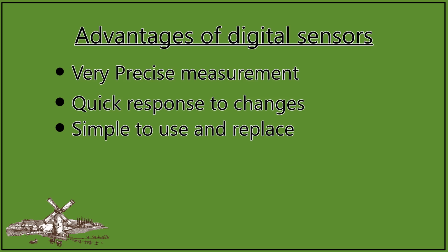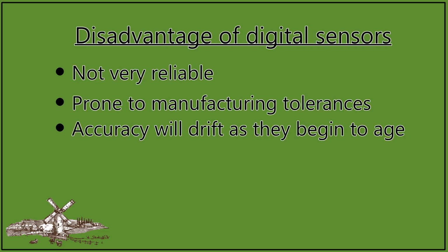Now, the disadvantage of a sensor like a temperature sensor or a humidity sensor is that they are not completely reliable. And what I mean by that is, if we were to buy 50 temperature sensors from the same manufacturer at the same factory, and we put them inside of an incubator which we know is 37.5 degrees Celsius, and I measured the temperature in my incubator 50 times using each one of those 50 sensors, I would probably get 50 different temperature measurements. And my temperature measurements will range anywhere from 36 degrees Celsius all the way up to 42 degrees Celsius.